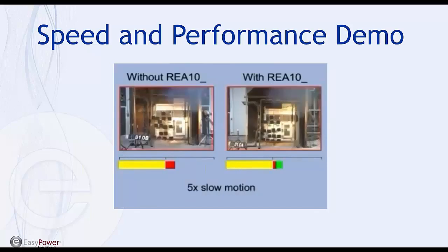So you can see it's a pretty serious condition on the left. You didn't have the fire, you contained the explosion, but just visually you can see just how much the explosion potential is reduced by having an REA arc flash relay that can operate in less than 2.5 milliseconds, which is just not much more than 1/10 of a cycle. So it's very fast and very effective.